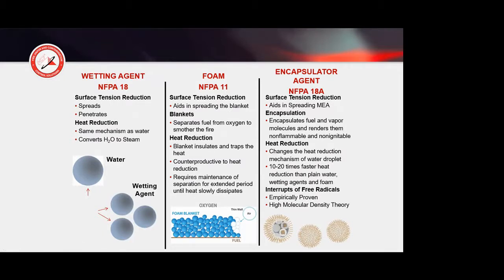across the flammable liquid. We see here that foam's basic building block is what we call a thin wall bubble structure. We put thousands of bubbles together, we form a blanket, we separate the fuel from the oxygen. And as we already talked about, some of the limitations there: it's counterproductive to the heat reduction, it actually traps in the heat. Here, the basic building block of an encapsulator agent is something called a spherical micelle. And we'll show that coming up next.